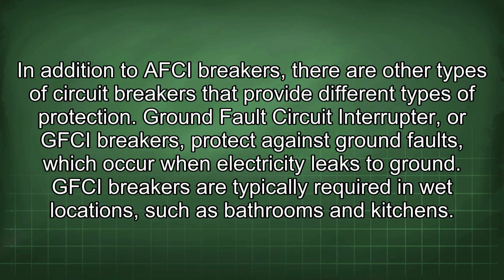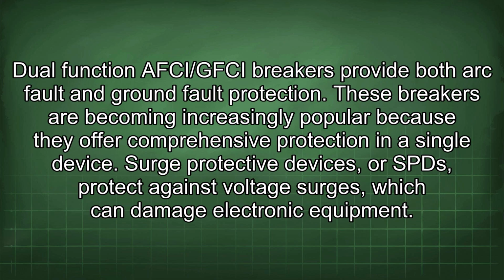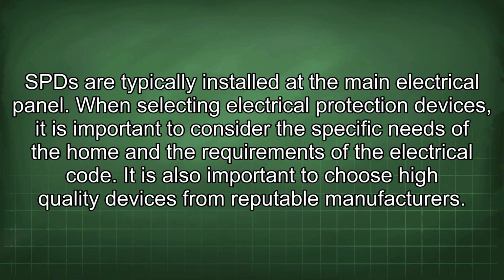In addition to AFCI breakers, there are other types of circuit breakers that provide different types of protection. Ground fault circuit interrupter, or GFCI breakers, protect against ground faults, which occur when electricity leaks to ground. GFCI breakers are typically required in wet locations, such as bathrooms and kitchens. Dual-function AFCI/GFCI breakers provide both arc fault and ground fault protection. These breakers are becoming increasingly popular because they offer comprehensive protection in a single device. Surge protective devices, or SPDs, protect against voltage surges which can damage electronic equipment. SPDs are typically installed at the main electrical panel.